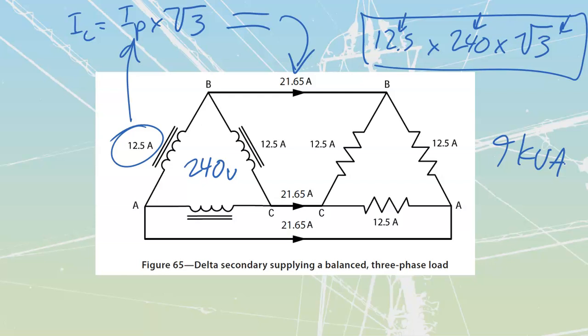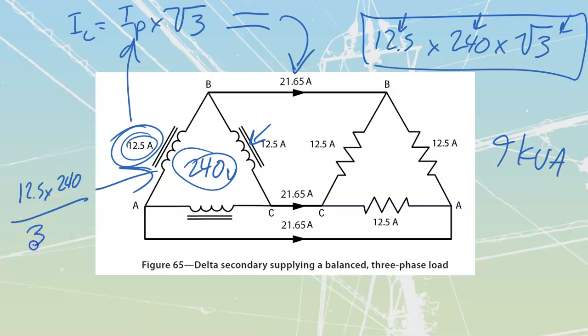Perfect. 9 kVA works for us. If we take the same transformers and look at the individual power, or VA, that each could do, if this is 12.5 amps and 240 volts, because we're only looking at a single one at a time, we don't need the root 3. 12.5 times 240 tells me that that is a 3 kVA transformer. This makes sense. A 3 kVA transformer over here, another 3 over here, another 3 over here, so our output should be 9 kVA.